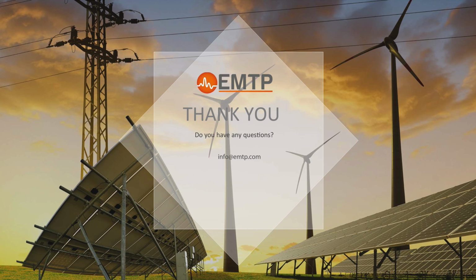Yep. Right now I'm using a simple file, but the actual research system is bigger than this, and we do have multiple weaker points in the system. With the PSO, we are also testing 2 plants on the same point of interconnection. That means the number of variables will be very high for 2 different plants. While optimizing, we are also considering 3 or 4 different contingency scenarios. This PSO will first run, and for those 2 PV parameters that we have, it will set some value.